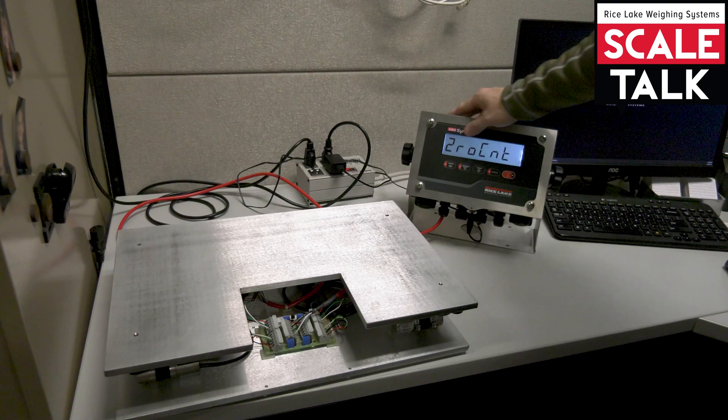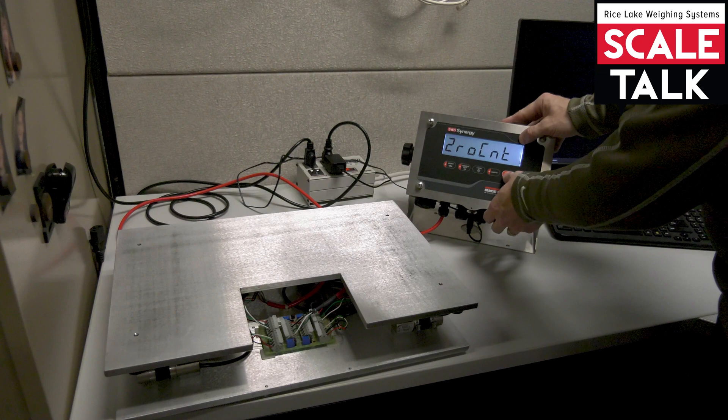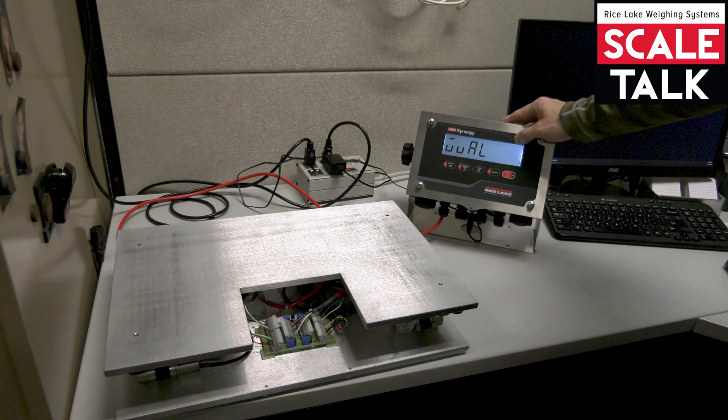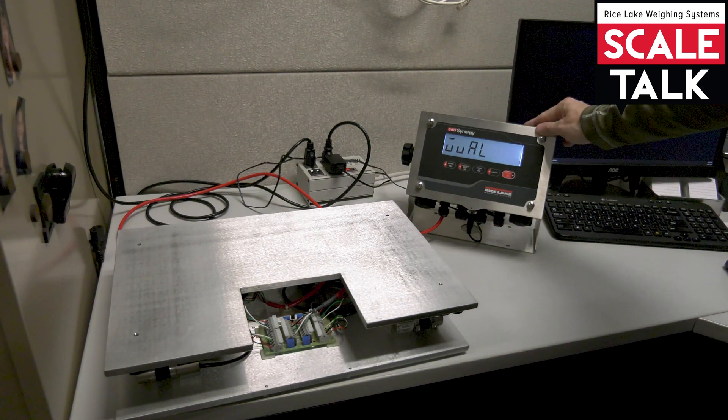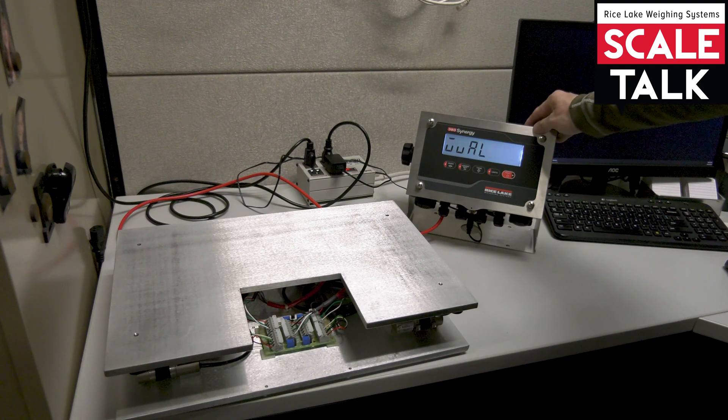At this point I have an option of reviewing the zero counts that it just captured. I won't do that now. I'll go to the right and I see the W-VAL. This is where we're going to enter the weight value that will be used for calibration.